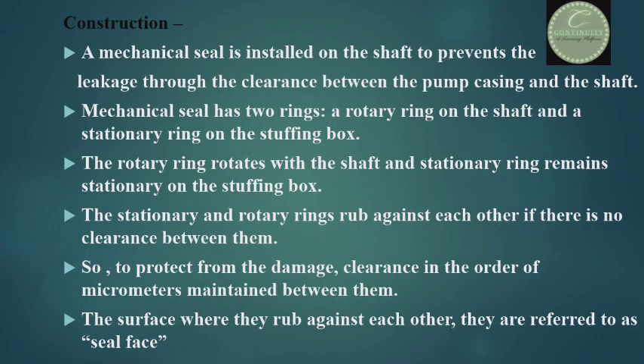Now about the construction of the mechanical seal — how is it made? A mechanical seal is installed on the shaft inside the stuffing box to prevent leakage through the clearance between the pump casing and the shaft. It has two rings: a rotary ring on the shaft and a stationary ring on the stuffing box.